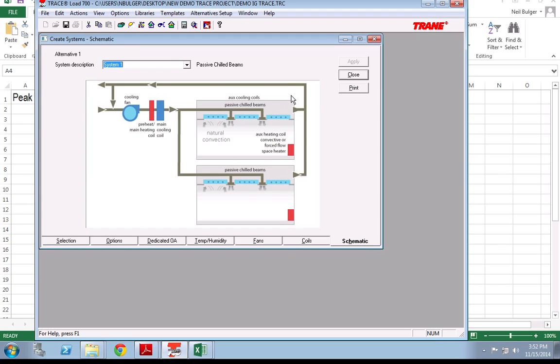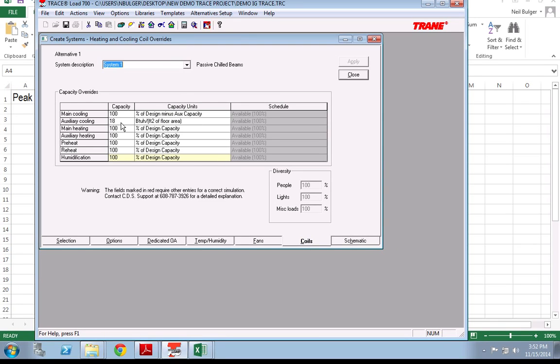More importantly, though, those zones that are not peaking and not going over their 18, those slabs won't contribute any cooling load to a slab that is peaking, because physically that couldn't be. A west zone could not transfer its heat to a north zone. So this setup is now going to give us some control. So this would actually work. So now if we ran this and we looked at the different reports, it would work in the capacity we want it to.